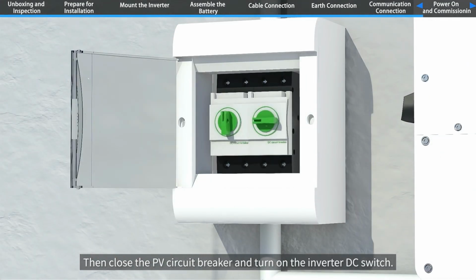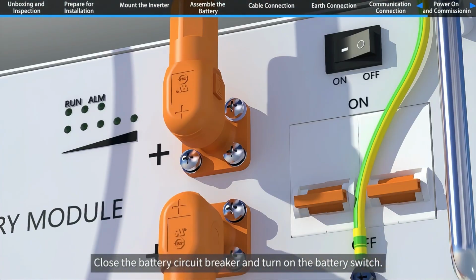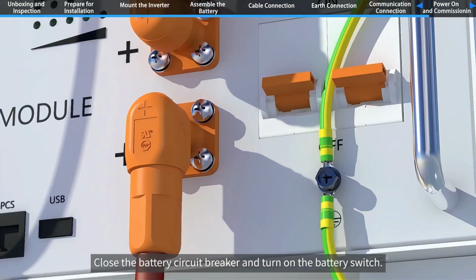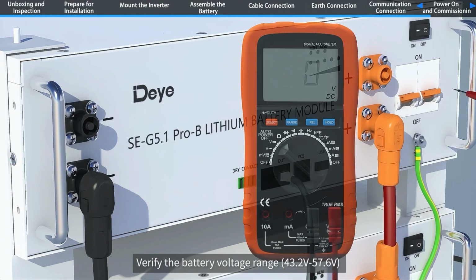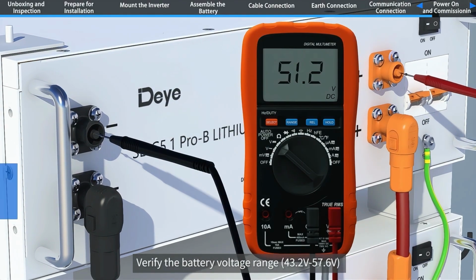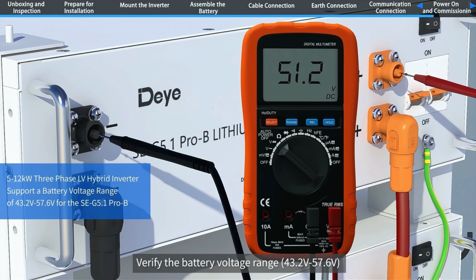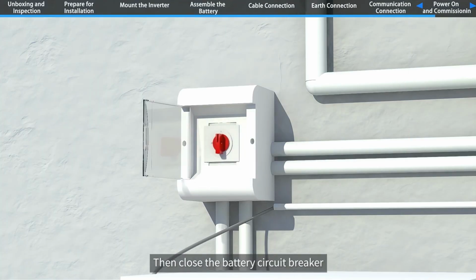Then close the PV circuit breaker and turn on the inverter DC switch. Close the battery circuit breaker and turn on the battery switch. Verify the battery voltage range, 43.2 V, 57.6 V. Then close the battery circuit breaker.